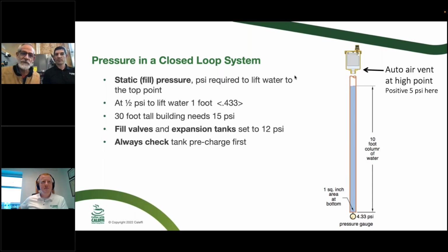If you round that up to 0.5, you'll get a little bit of positive pressure, because at the highest point in that building, at the top of the riser, maybe the boiler's up on the top floor of a high rise in New York City or something, we want to have at least a 5-pound pressure up there. And that makes sure that when we have a float type of air vent, we have enough pressure to make sure the float goes up and seals tight against its valve. So there's a number, there's the math, there's a little graphic of how it works.